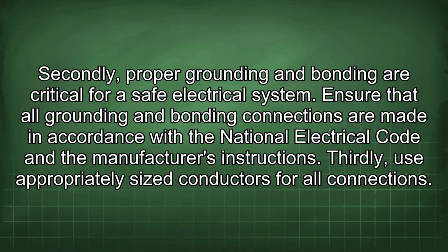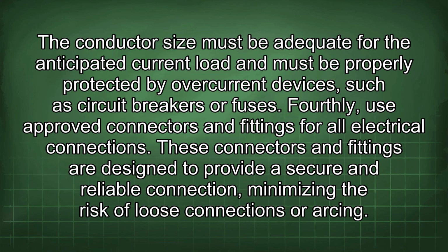Secondly, proper grounding and bonding are critical for a safe electrical system. Ensure that all grounding and bonding connections are made in accordance with the National Electrical Code and the manufacturer's instructions. Thirdly, use appropriately sized conductors for all connections. The conductor size must be adequate for the anticipated current load and must be properly protected by overcurrent devices, such as circuit breakers or fuses.